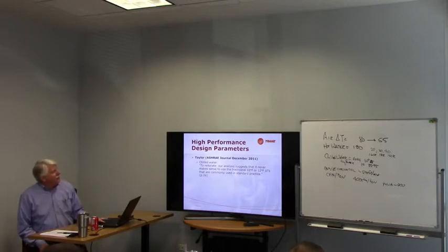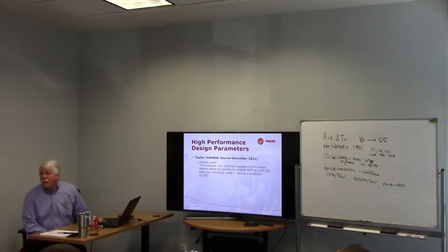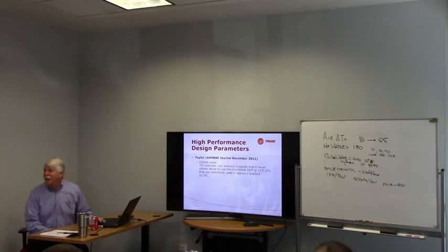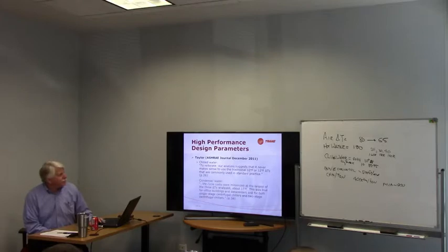They suggest that it never makes sense to use the traditional 10 or 12 degrees that are commonly used. So anytime you see a system designed that way, the engineer typically has taken something that he's done before and he's regurgitating it for another job rather than do more design work. It says if life cycle costs were minimized at the largest of the 3 delta T's, about 15 degrees for the condenser water, that's 2 GPM instead of 3 GPM per ton, and that means 67% of the flow, which is 0.6 times 0.6 times 0.6 for energy savings. Okay, so you can see there's a lot of energy to be saved there.